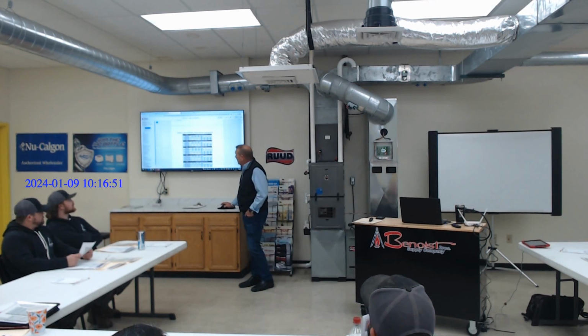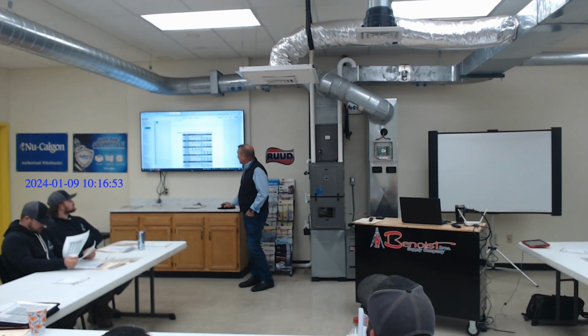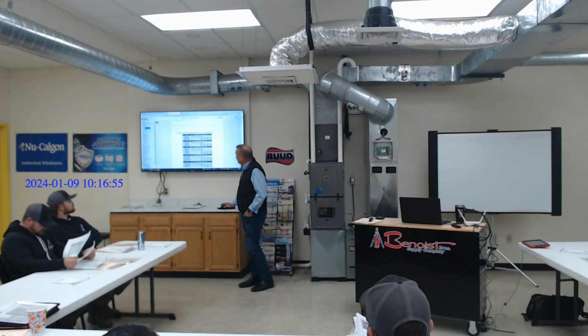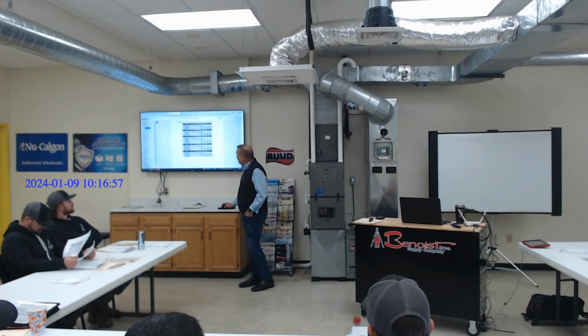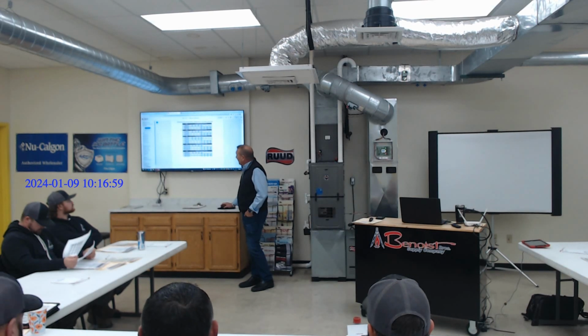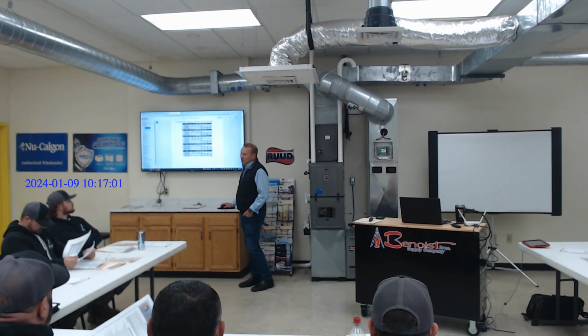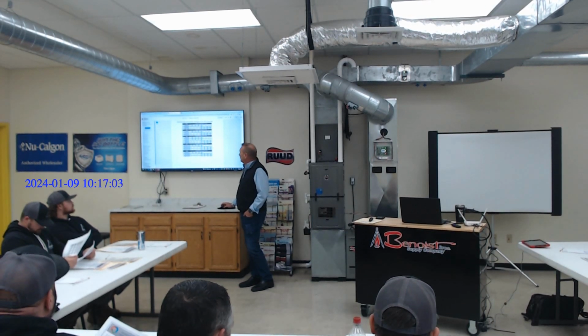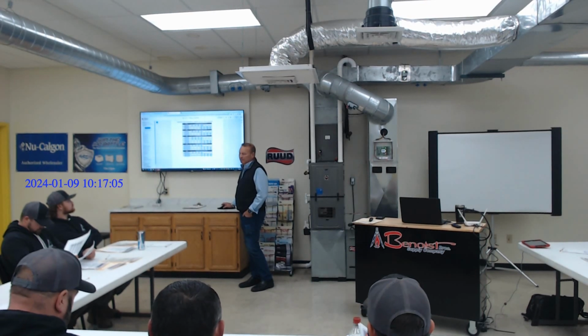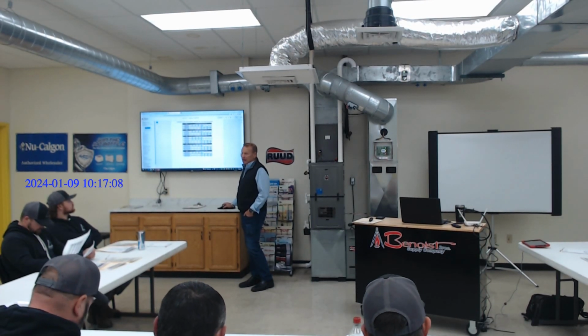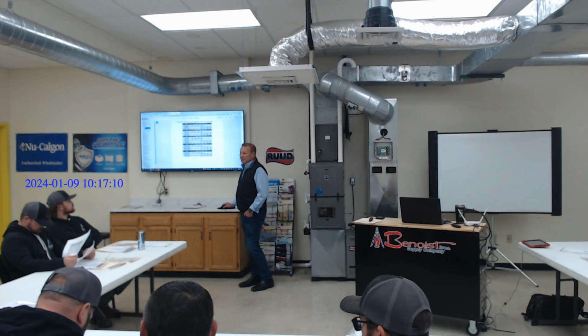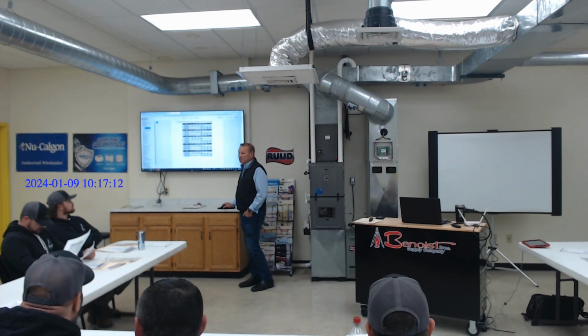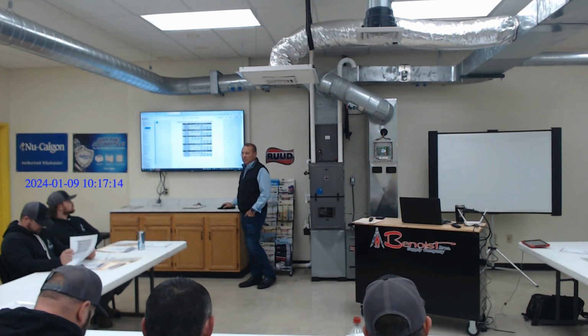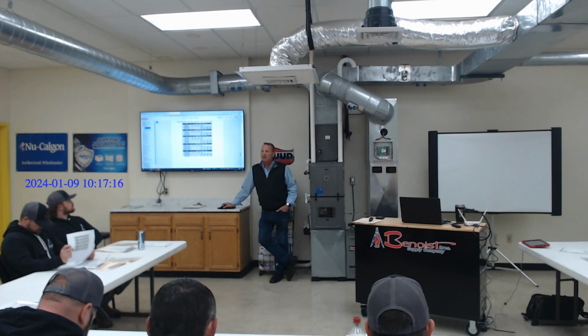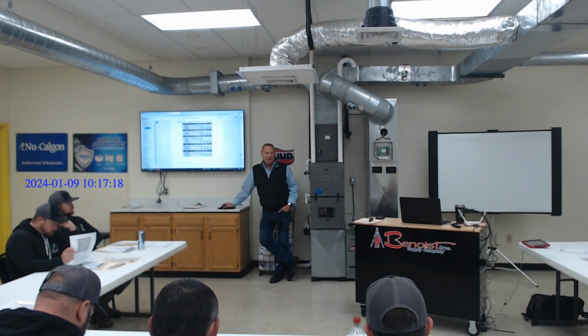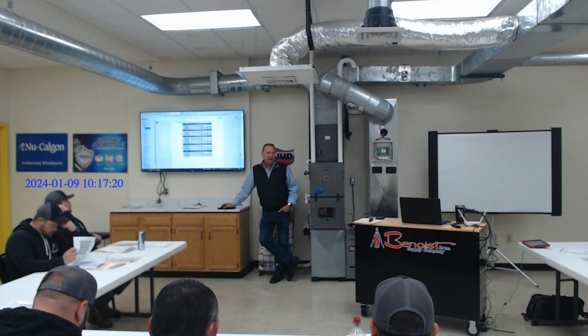this might help you with your non-communicating 2-stage, your minimum airflows. Outdoor unit size, minimum airflows. So when you're non-communicating outdoor and you're communicating indoor, this is the minimum airflows you need per size, right? Again, the key here is the CFMs to the zones and what size equipment we're working with, and understanding on the 2-stage where you're at, if it's non-communicating. Does that make sense?